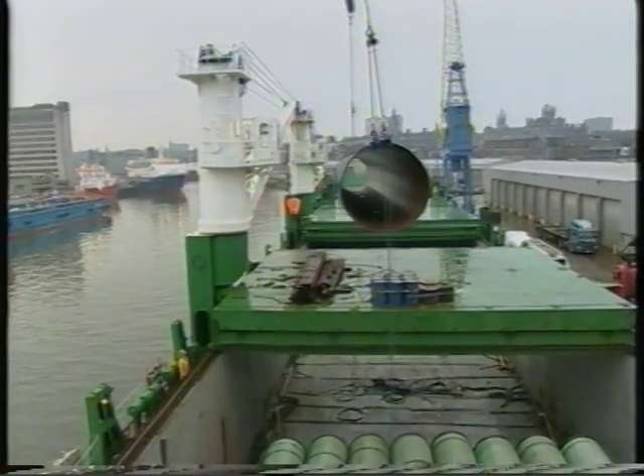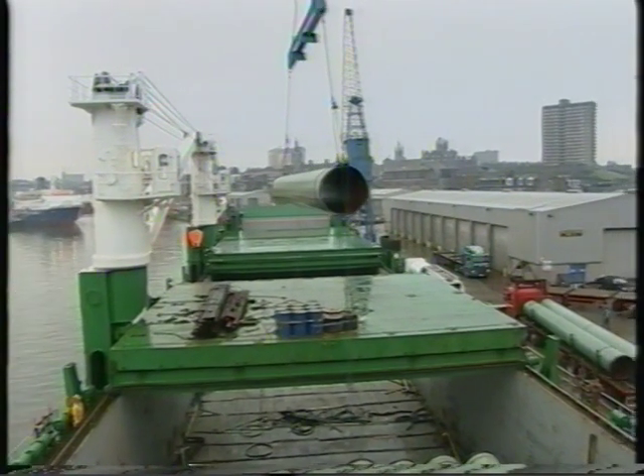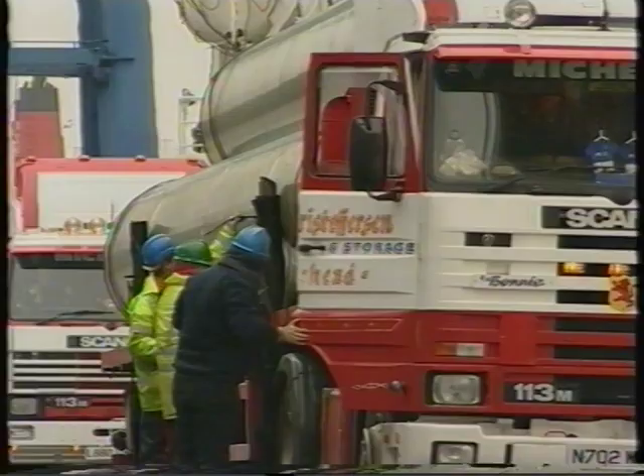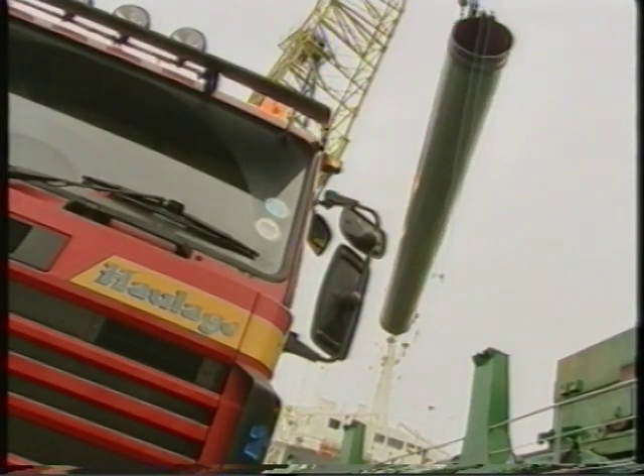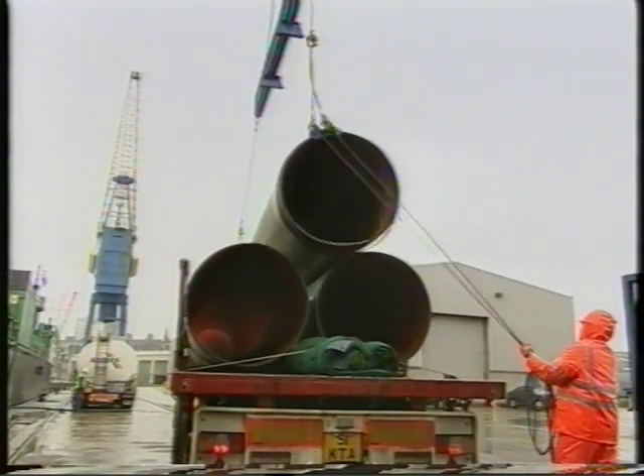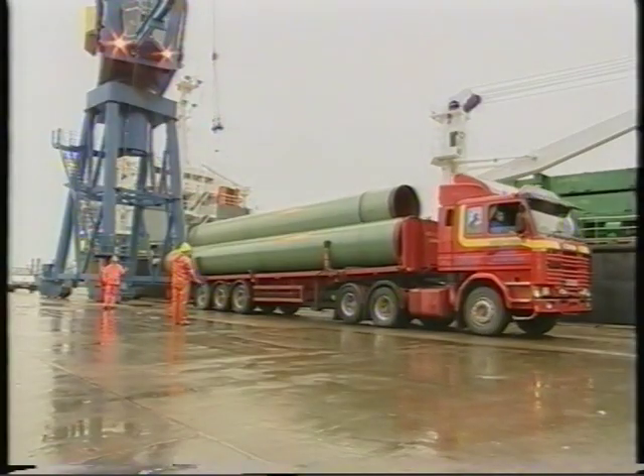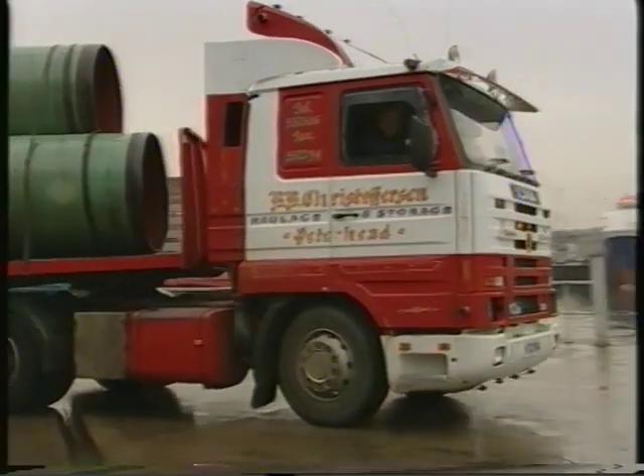Meanwhile, over 32,000 tonnes of 1.2-metre diameter pipe was shipped from the manufacturers in Italy to Aberdeen. The 70-kilometre pipeline required 6,000 sections of pipe. Averaging 12 metres in length, the pipes had a higher carbon content than traditional pipeline steel. This made the pipe stronger, allowing it to carry greater pressure, while reducing the thickness of the material. The result was a large reduction in the weight of the material being transported.